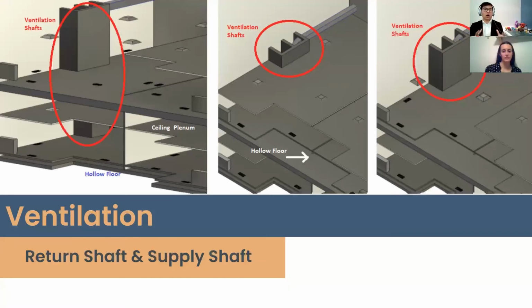So with our project in mind, if you look at specifically the images circled in the figure above, you'll notice that the supplied air is pushed through the main supply trunk and ducted above to the hollow floors of the zone. This fed air is then released into the zone via perimeter linear floor grills, and as the air is warmed by human activity, it rises to the vaulted ceiling space or plenums, where it is then sucked and returned to the DOAS via one of the many return shafts spanning all 6 levels of the residential building. And as a result of taking advantage of the stack effect, apart from ductwork connecting the DOAS to the return shafts, no ductwork is actually present for the return of the building's ventilation.